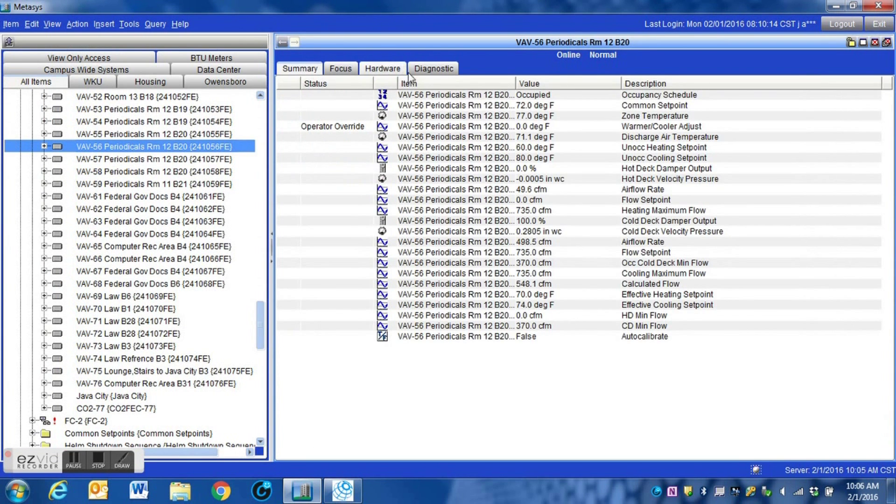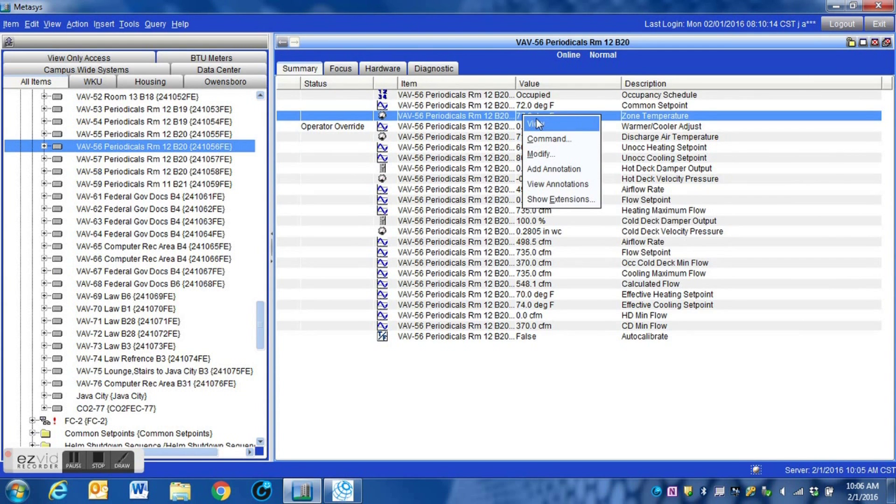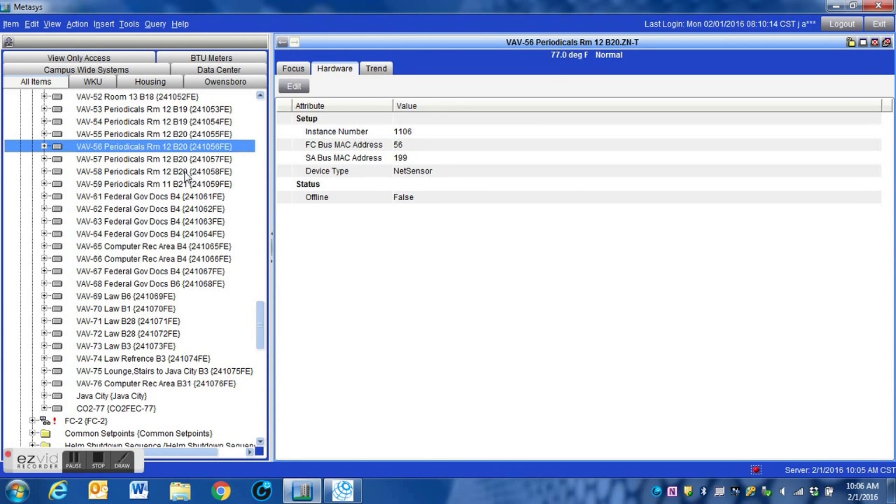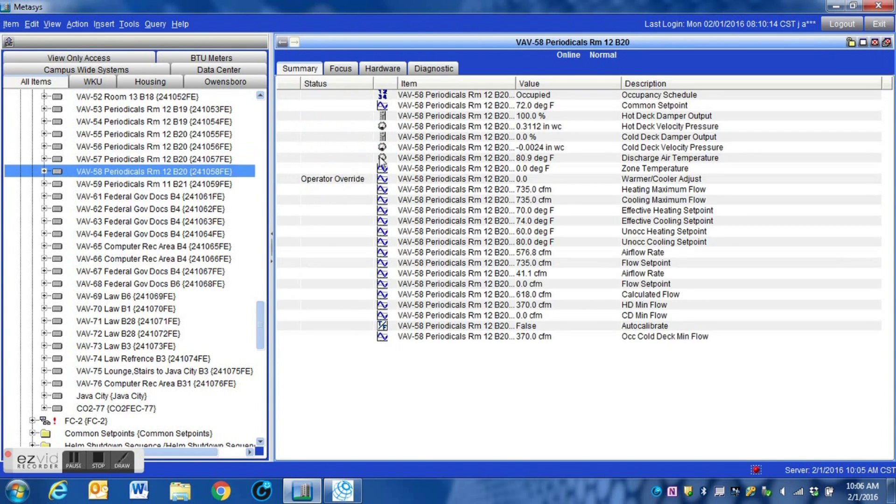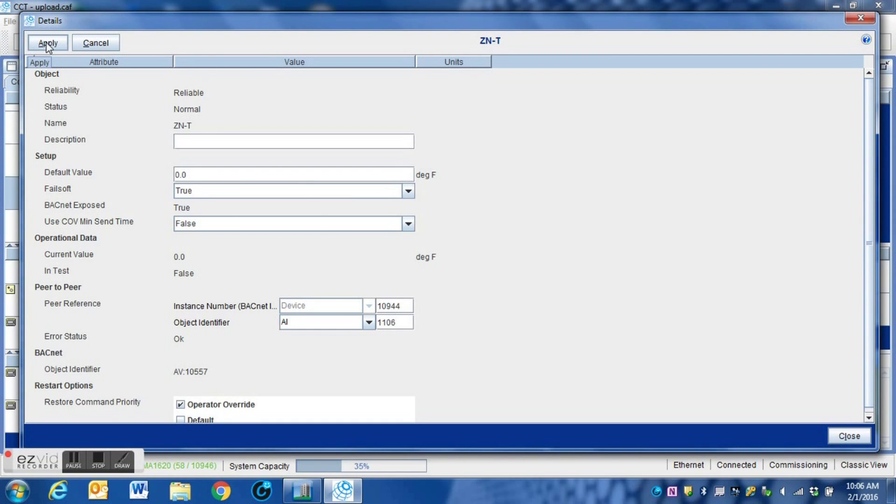Now then, I've got to also get the instance number for the zone temp itself. View the zone temp, click hardware, and here is the instance number for that particular software point. That is what we're going to be writing into this controller here. Once again, I enter that information into this box, and as soon as I hit apply, it will start receiving information.